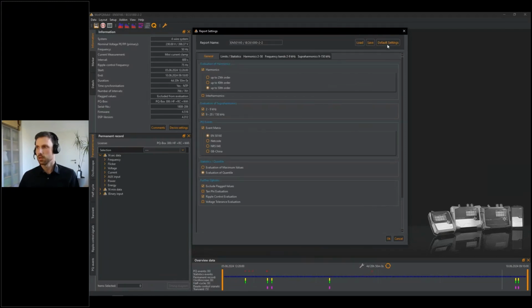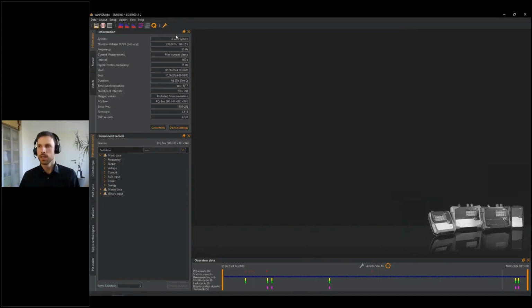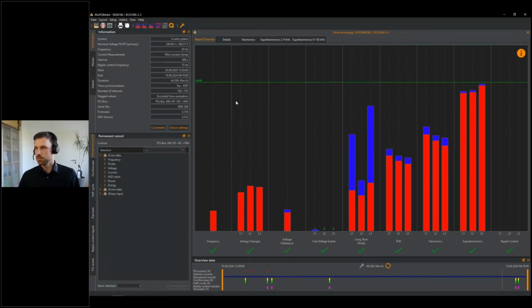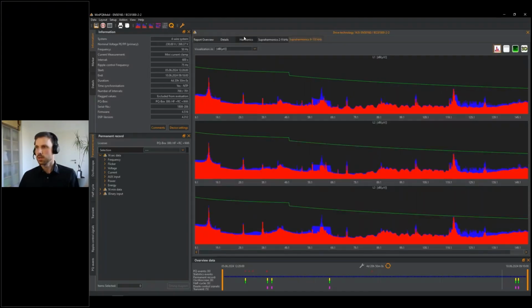By default, PQ-Mobil, if I click on Default Settings, we go with the EN 50160, and the values that are not covered in the 50160 will be completed with the values from 61000-2-2, as both are almost the same values, and they're both for public grids. So with this evaluation, I can click on OK, and this button, at the very top, Norm Evaluation, with one click, I will get an overview. And now I see, okay, there is a field with supraharmonics, and if I click on that, I will see the values of the supraharmonics. So another tab opens within the report.